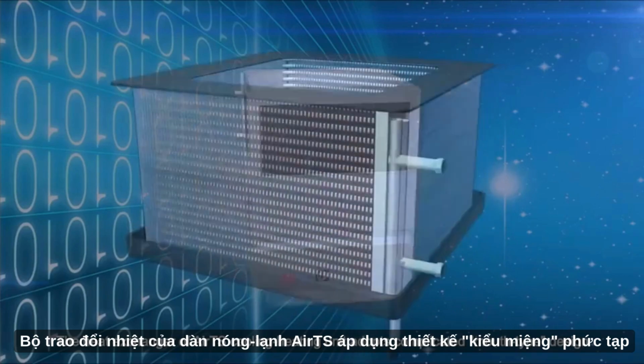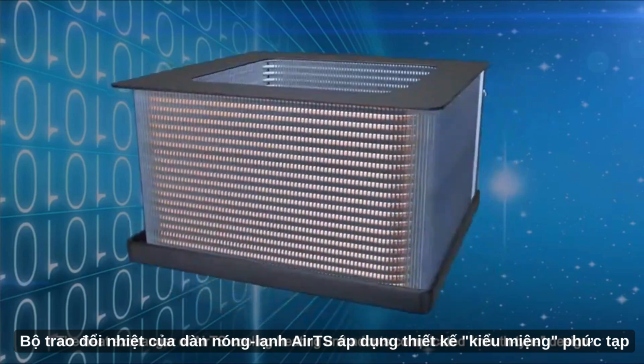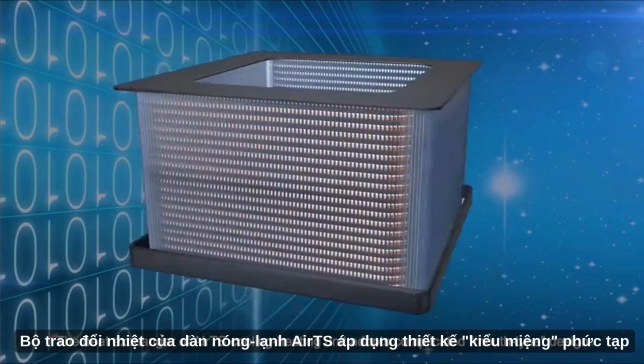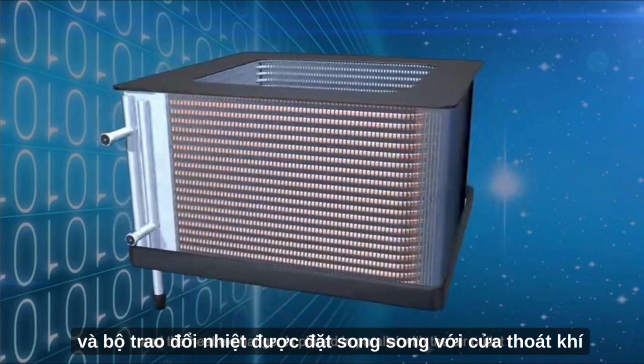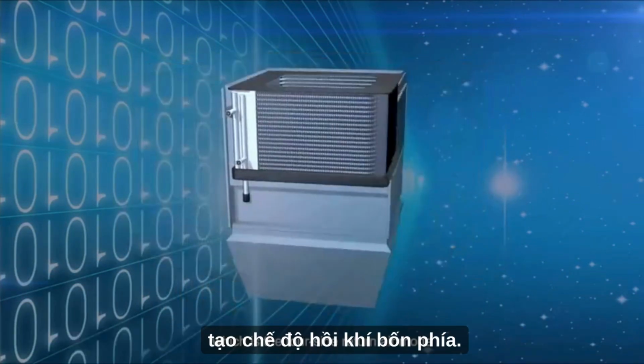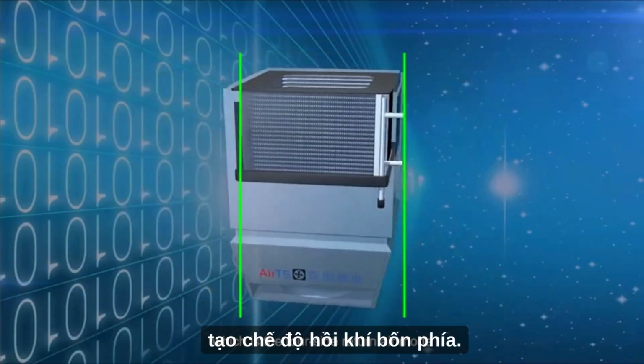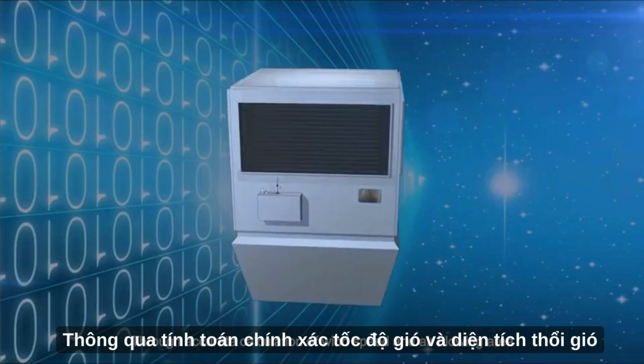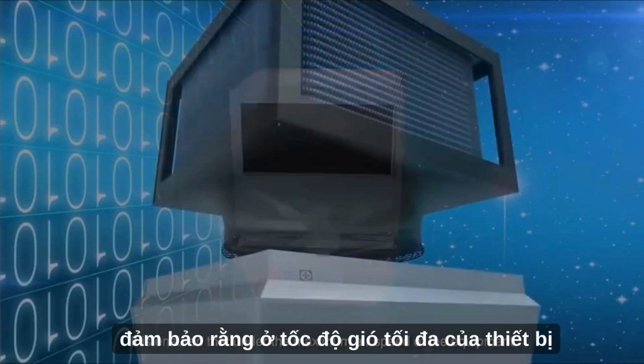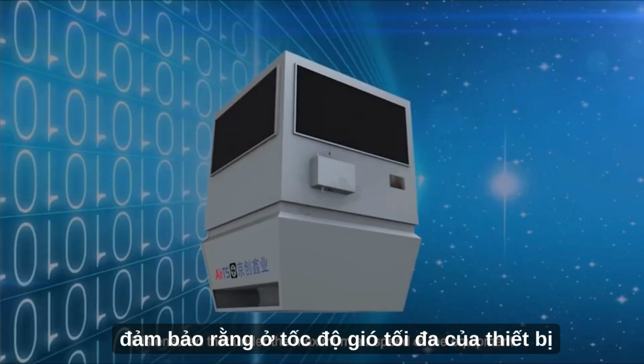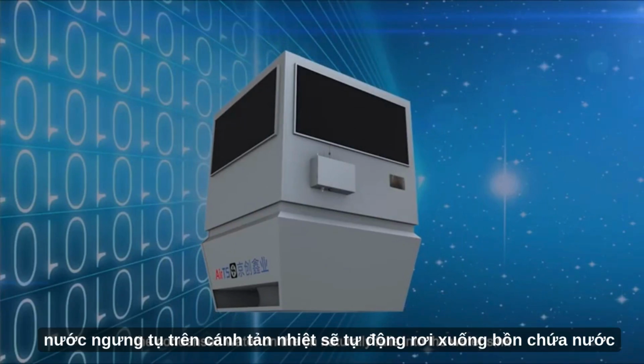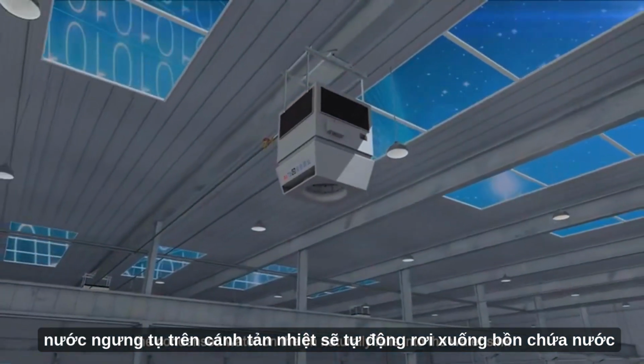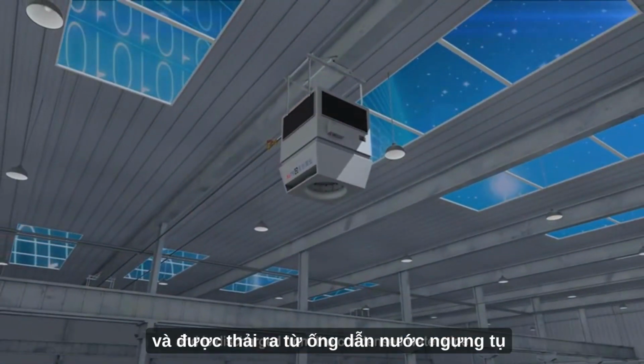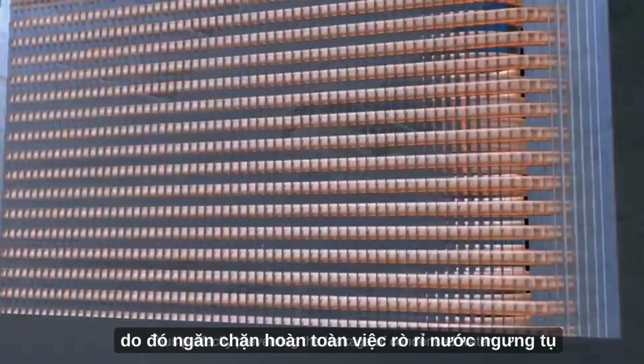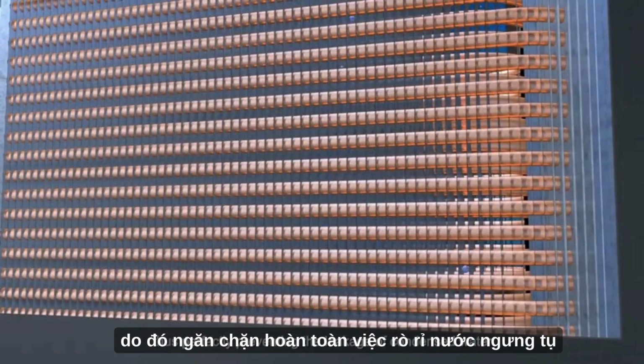The heat exchanger of AirTS cooling heating unit adopts complicated mouth-type design, and the heat exchanger is placed in parallel with the air outlet, which is the four-side return air mode. Through accurate calculation of wind speed and air blowing area, it is ensured that under the maximum airspeed of the equipment, the condensed water on the fin naturally falls into the water sink and is discharged from the condensed water pipe, thus perfectly preventing the leakage of condensed water.